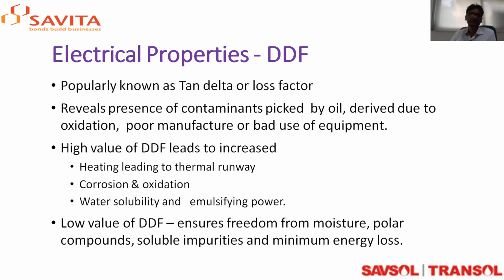This dielectric dissipation factor is sometimes affected by soluble water. Suppose there is water solubility, or certain emulsifiers that enter the oil because of paints used to seal the edges of the metal, or resinous material used inside the tank for strength, or from corrugated papers or pressboard wood. If such emulsifiers come into the oil, they will affect the dielectric dissipation factor, or loss factor.